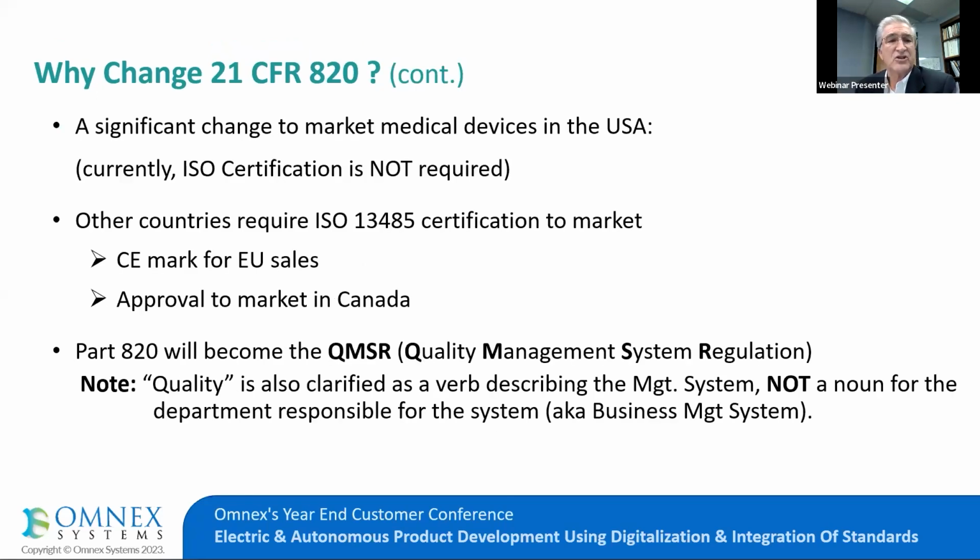The significant change to us in the U.S. is that currently ISO certification is not required to start a 510(k). Unlike Canada or the EU, where to apply for a CE mark or market in Canada, you must have a certification to even begin talking. So I expect the U.S. may follow in their footsteps.